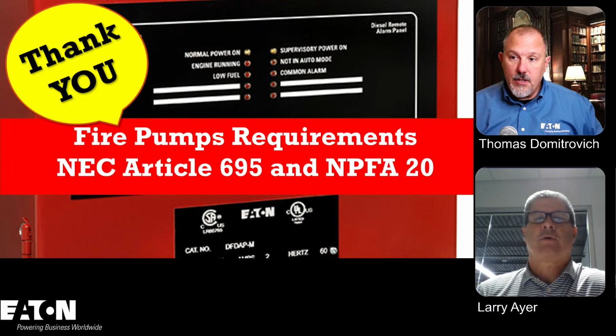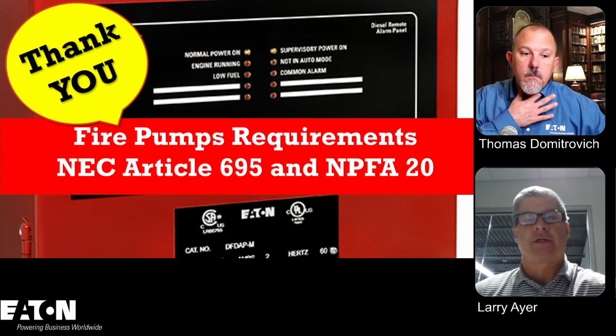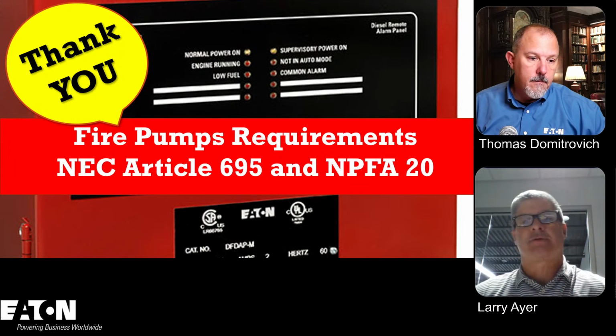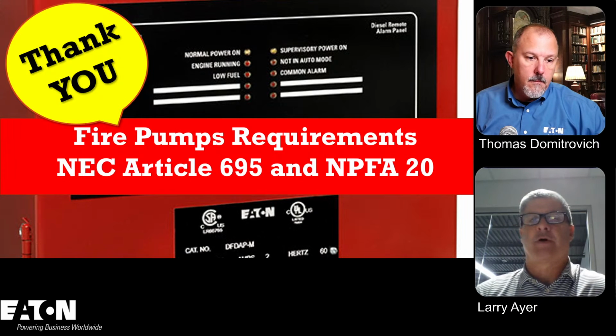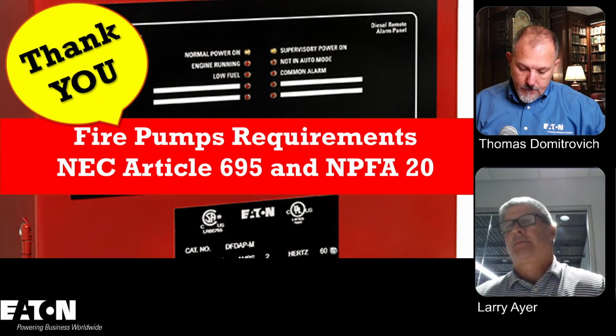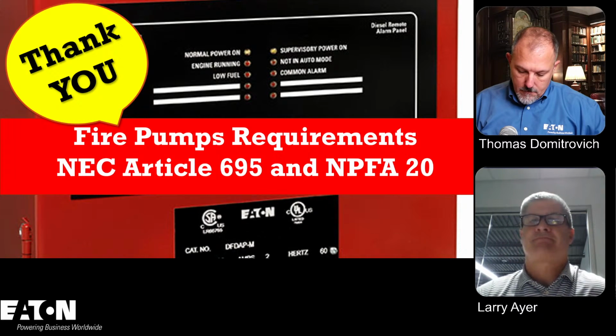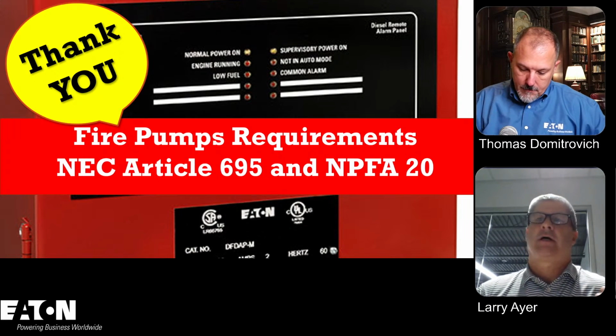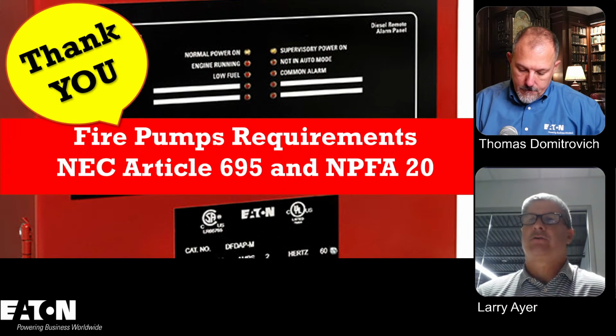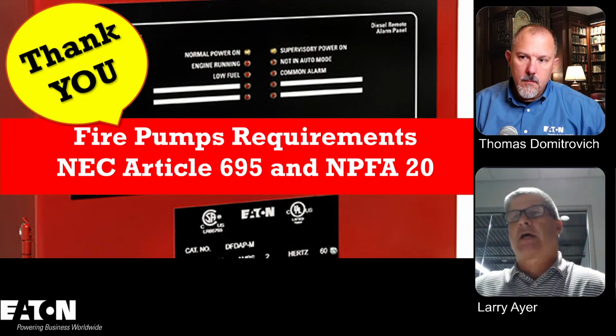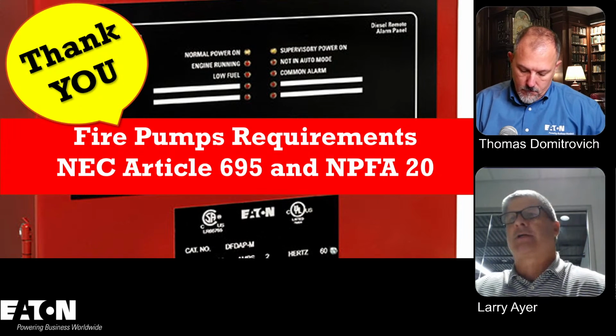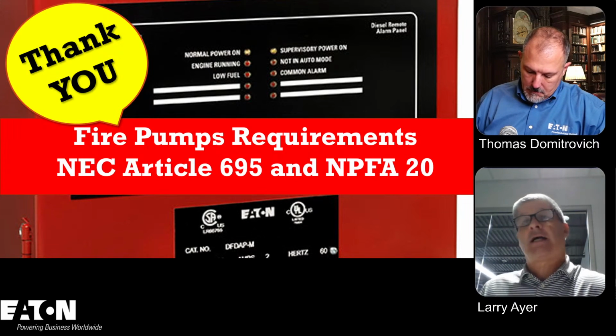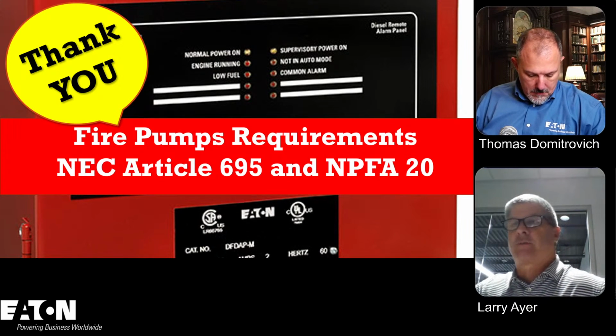Now one of the other questions in there is that someone mentioned, and it's true, Bruce noted that the voltage drops do not apply. So the 15% voltage drop for startup of a motor doesn't have to apply for genset supplied power, and that's true because there's an exception in 695. But my experience is that when you have things of that nature for voltage drop, and you use transformers, you always got to worry about alternate sources of power with generators and transformers: when you start and stop transformers, you got to make sure that you size your overcurrent protection to handle that inrush. So, even though you don't want to, you got to make sure your overcurrent devices are sized high enough so they don't nuisance trip when you transfer power.